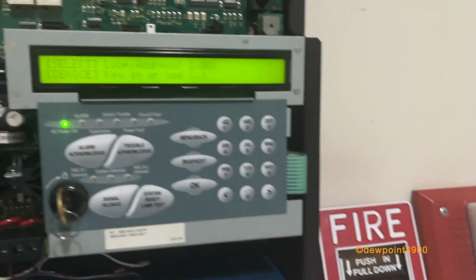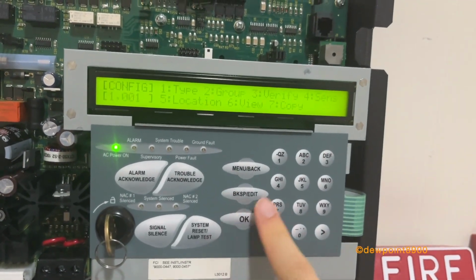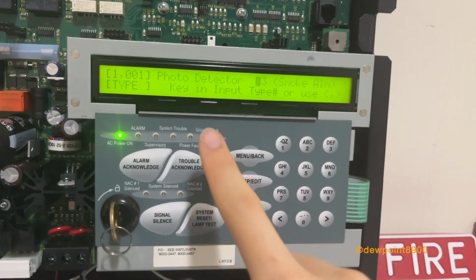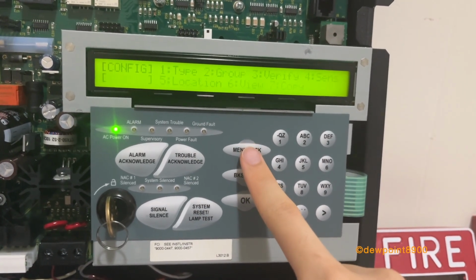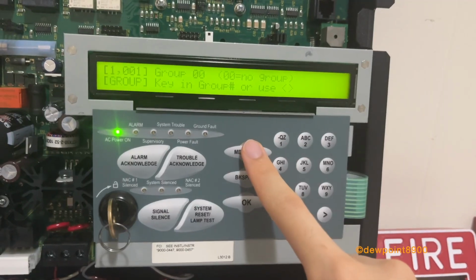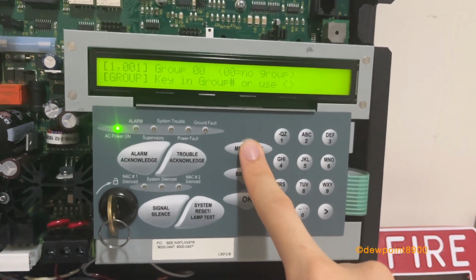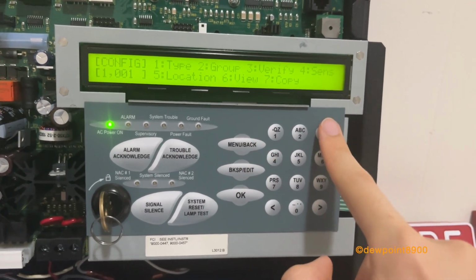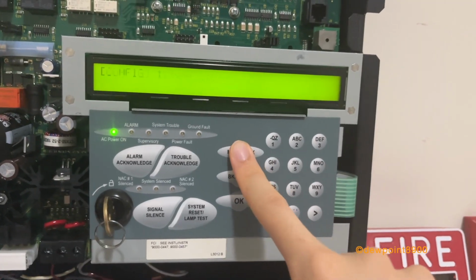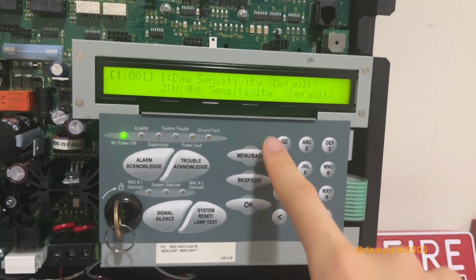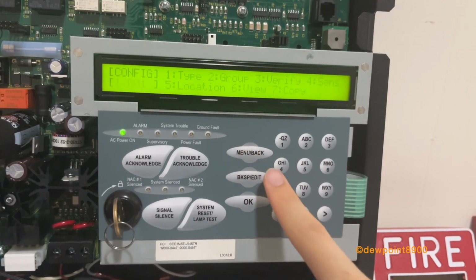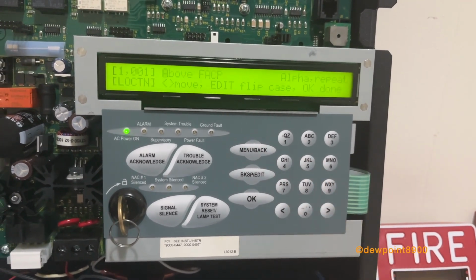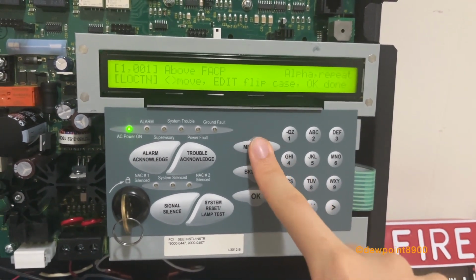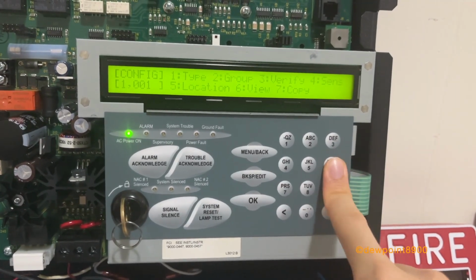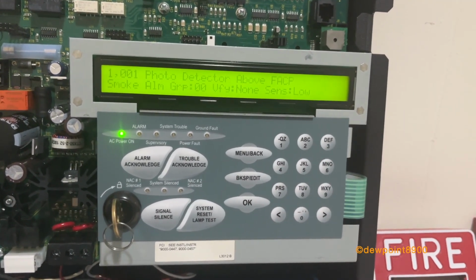Select an address for the device. This is the detector. Go to type. Photoelectric detector. Two is the group, set to no group, but each device could be assigned a group for correlations. Three is verification, just default. Sensitivity, there's day and night sensitivity, they're both default. Five is the location, which is just the label for that device. And six is view, which shows a summary of this device and its configuration.